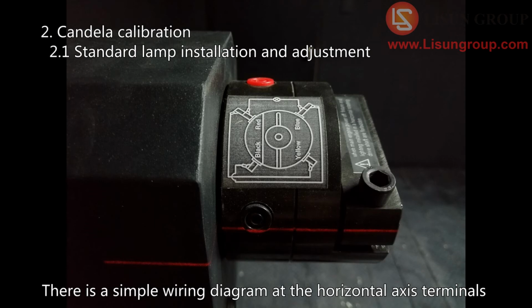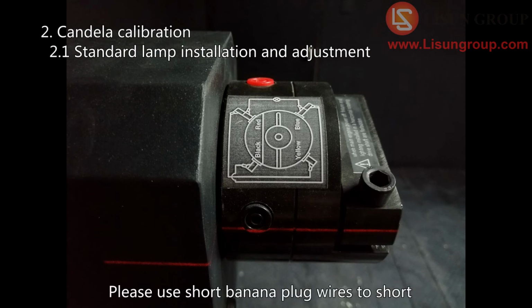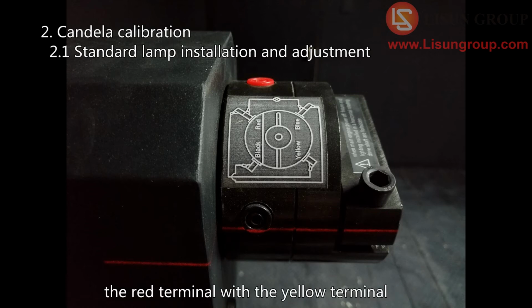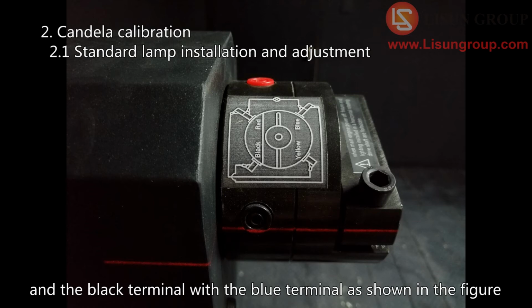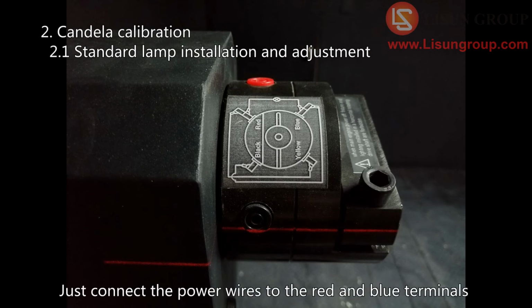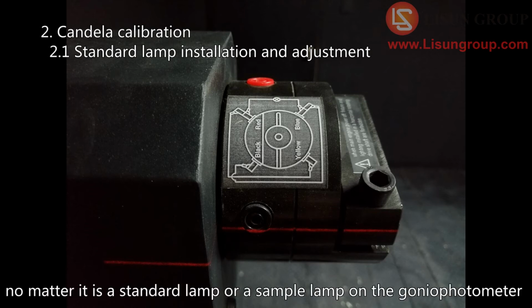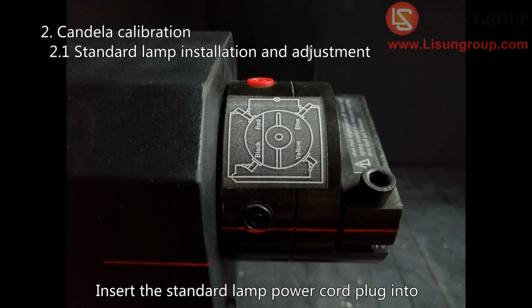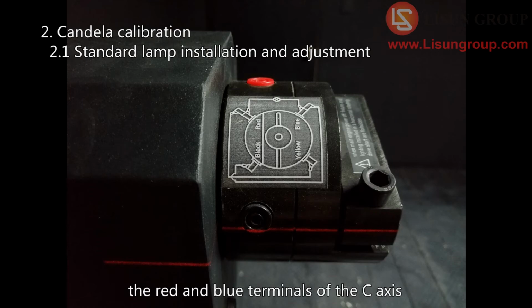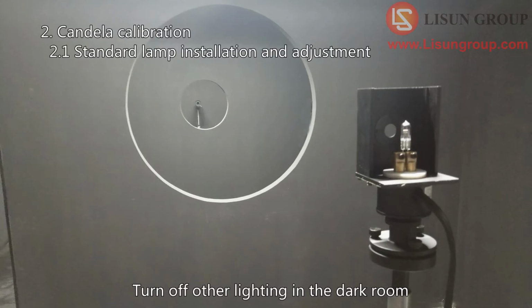There is a simple wiring diagram at the horizontal axis terminals of the goniophotometer. Please use short banana plug wires to short the red terminal with the yellow terminal, and the black terminal with the blue terminal as shown in the figure. Just connect the power wires to the red and blue terminals no matter it is a standard lamp or a sample lamp on the goniophotometer. Insert the standard lamp power cord plug into the red and blue terminals of the C-axis. Turn off other lighting in the dark room, and close the door of the dark room.